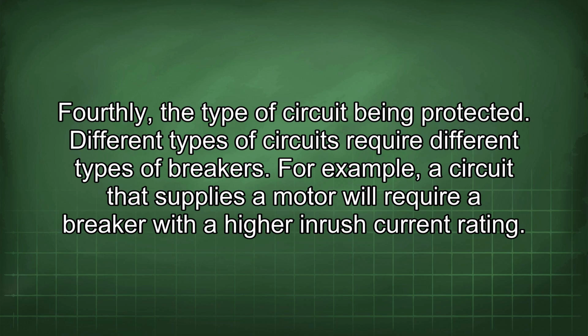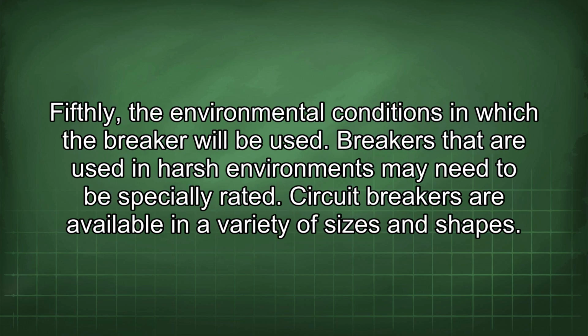Fourthly, the type of circuit being protected. Different types of circuits require different types of breakers. For example, a circuit that supplies a motor will require a breaker with a higher inrush current rating. Fifthly, the environmental conditions in which the breaker will be used. Breakers that are used in harsh environments may need to be specially rated.